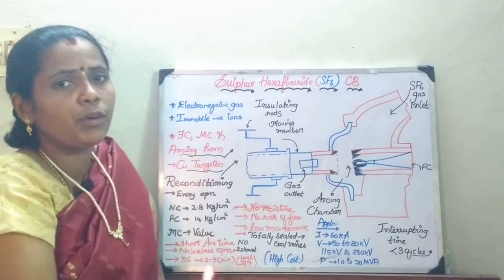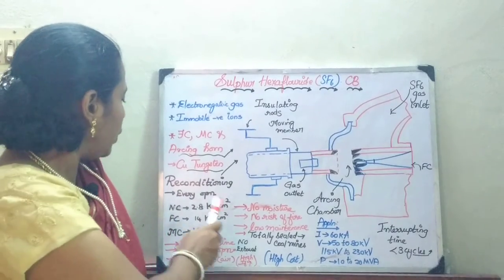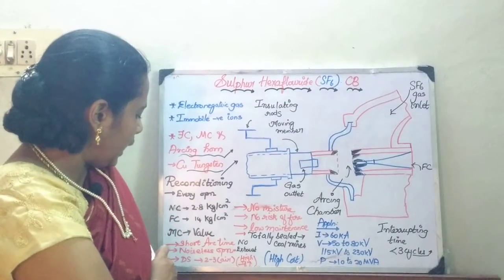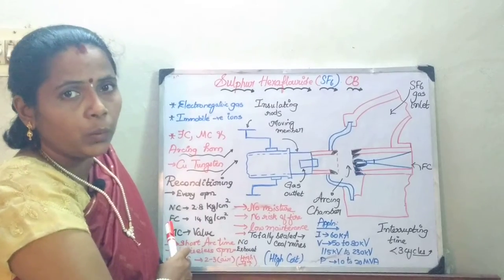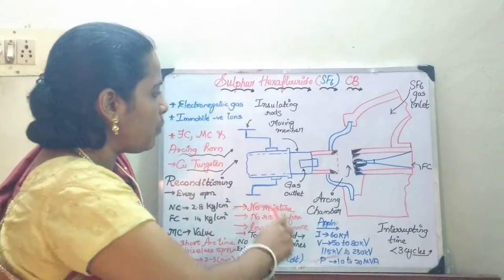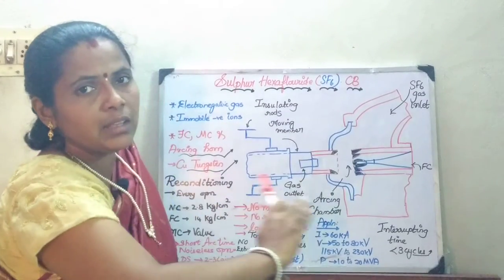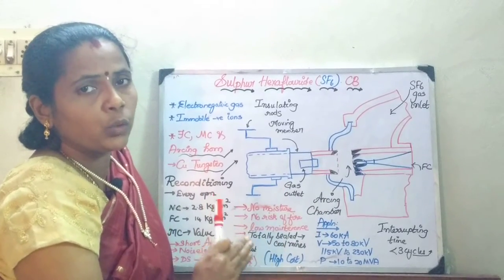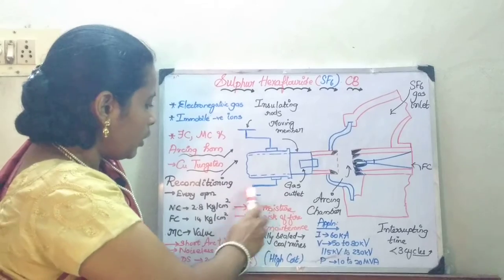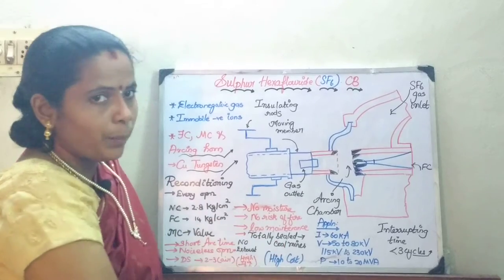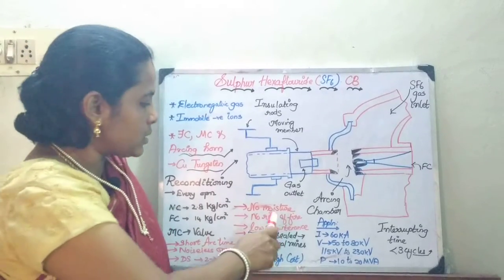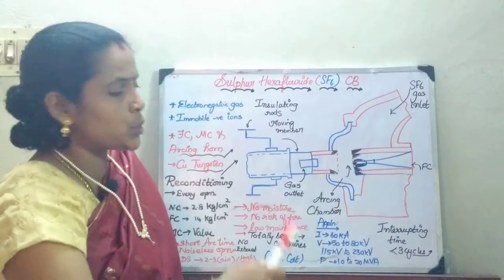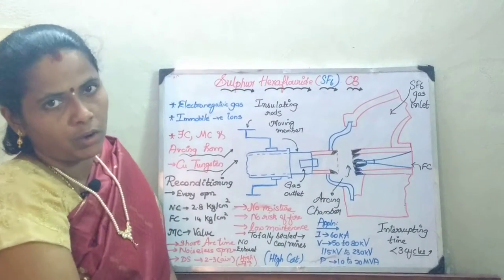The reason for going with SF6 is that it provides a short arcing time and a noiseless operation because everything is neatly sealed. Whenever it is neatly sealed, you can have a moisture-free operation. The risk of fire is also eliminated, which leads to a lesser maintenance cost.